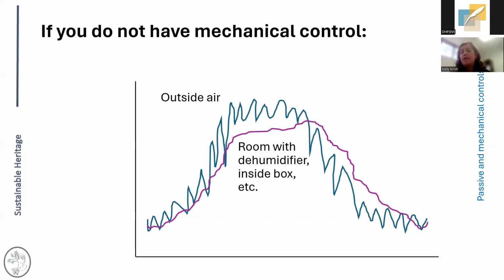The other option, if you don't have mechanical control, is to move further on in those levels of control and pull up the dew point graph for wherever you might be monitoring elsewhere. So if you have a dehumidifier or a humidifier running within a space, you can pull that up with the outside air and see what the difference is.